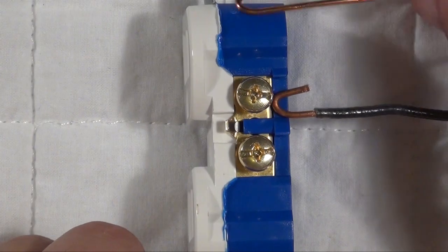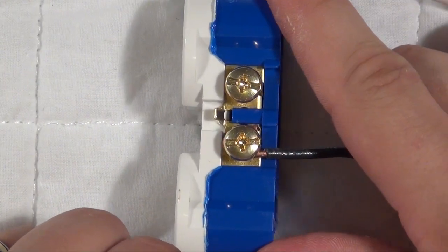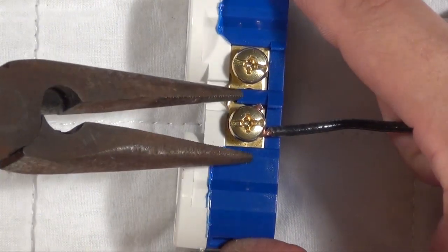We will start by connecting the black wire to the brass screw. In most cases, you will see two brass screws on your outlet. With this particular installation, either screw will work. For the brass screw facing up, place your black wire loop around the brass screw. Be especially careful to make sure that your loop follows the clockwise rotation around the screw.